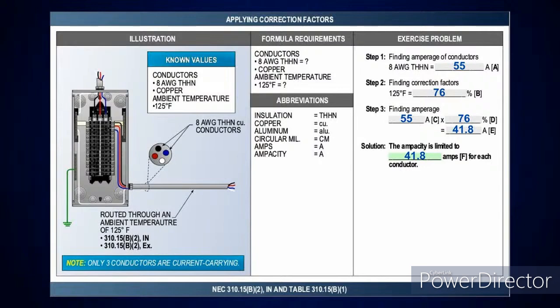I know what you're talking about. All right. Same thing here. It's THHN. I'm still at table 310.16. I pick up a number 8 in the 90-degree C column. It tells me it's good for 55 amps. Then I look at table 310.15(B)(1), pick up in the far right-hand column, come down, find where I'm in the range for 125 degrees Fahrenheit, come across, and pick up the 90-degree C column. It's going to tell you that you have a derating factor of 76%. So it's pretty basic. 55 amps times 76% gives me 41.8 amps for each conductor.